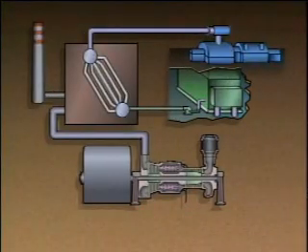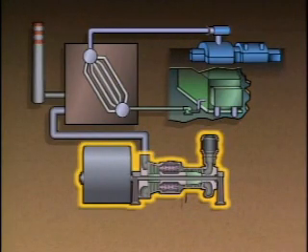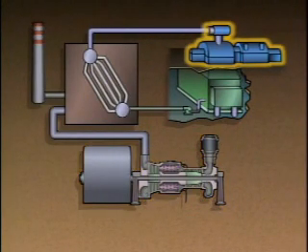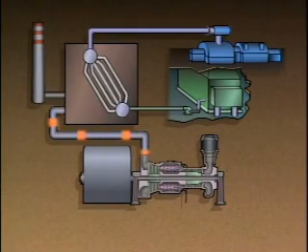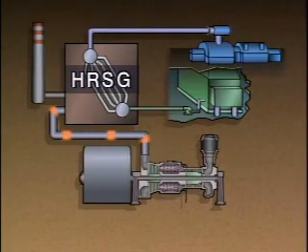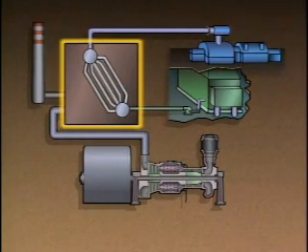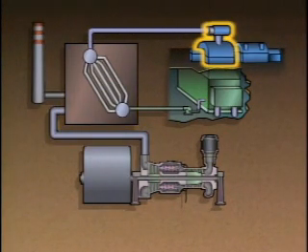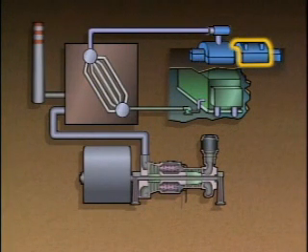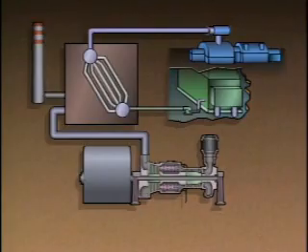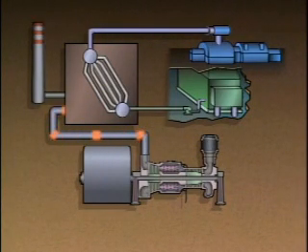In a combined cycle plant, the exhaust gases from a gas turbine are used to produce steam to drive a steam turbine. The hot exhaust gases that leave the gas turbine are routed to a heat recovery steam generator, or HRSG. In the HRSG, the exhaust gases transfer heat to water to produce steam. The steam is sent to the steam turbine, where some of the energy in the steam is converted into mechanical energy, and then into electricity by a second generator. This increases the efficiency of the plant, since more of the energy in the exhaust gases is used before they are released.